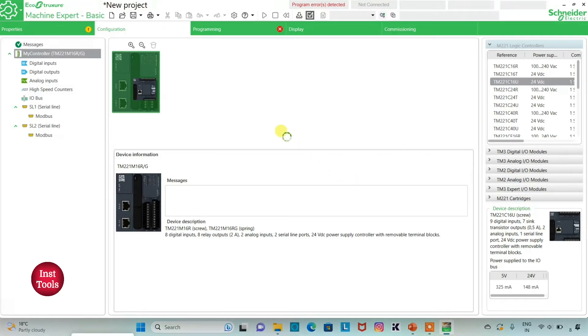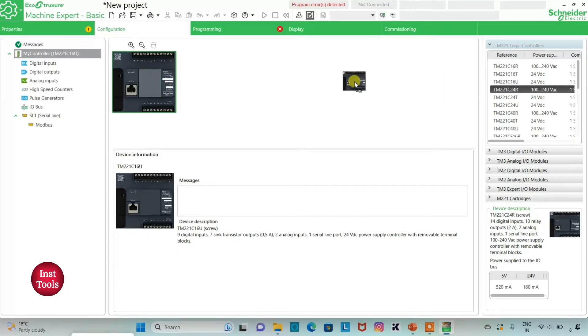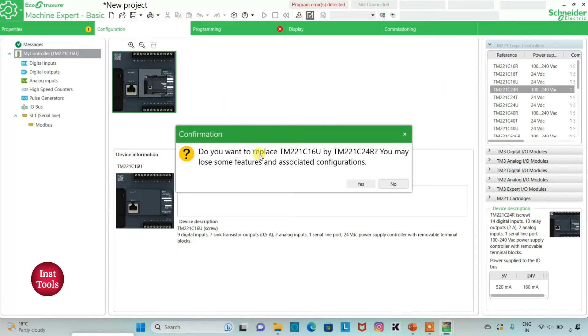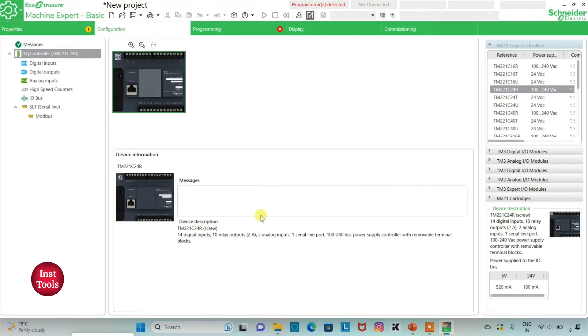If my selection changes and I need to select TM221C24R instead, I will click on it, drag it here, and click Yes to replace — you may lose some features and associated configurations. Here is a description of the device TM221C24R: it has 14 digital inputs, 10 relay outputs, 2 analog inputs, 1 serial line port, and a 100 to 240 volt AC power supply controller with removable terminal blocks.